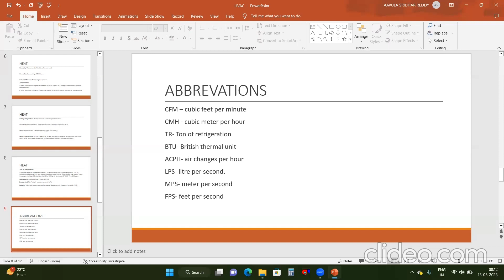ACPH, air changes per hour. How many times the air has to be changed inside the room in an hour is called ACPH. This is used in toilet ventilation systems, kitchen exhaust systems and staircase pressurization. And liter per second, LPS, is another form of CFM measurement, if we are using metric units. MPS, meter per second, is velocity, and FPS is feet per second. To measure the velocity, we use these two terms, MPS and FPS.